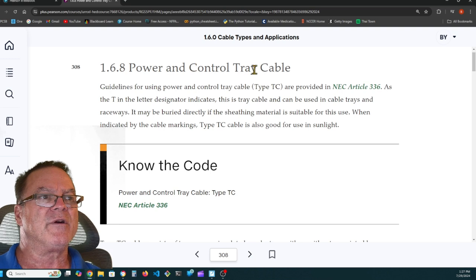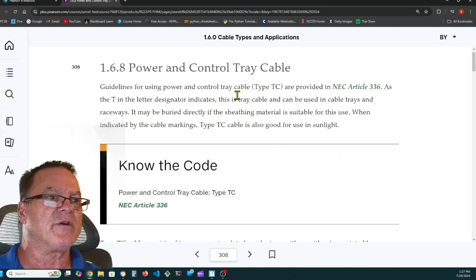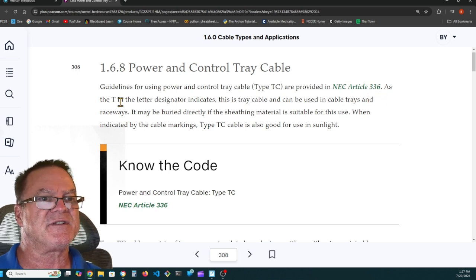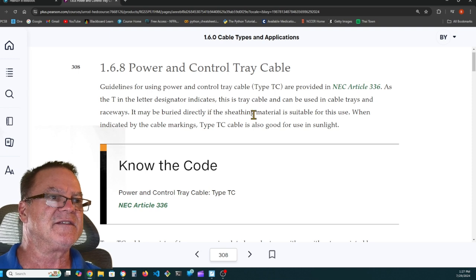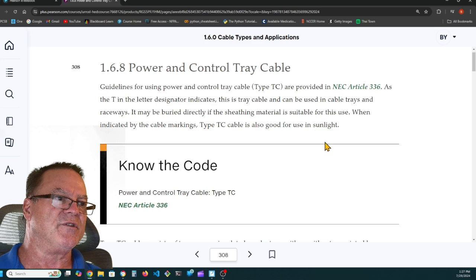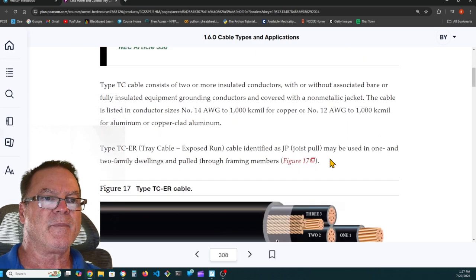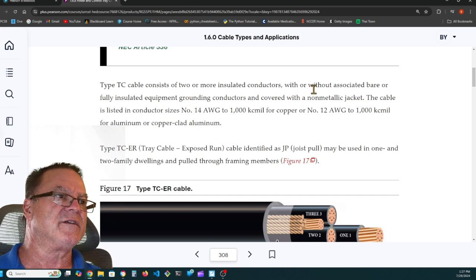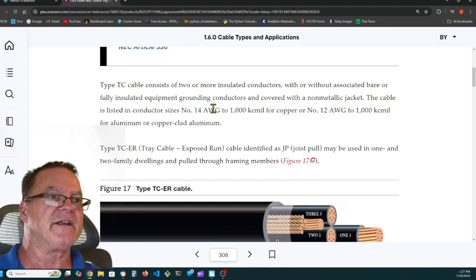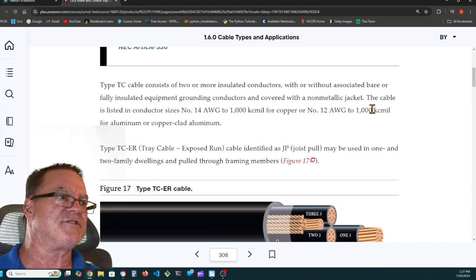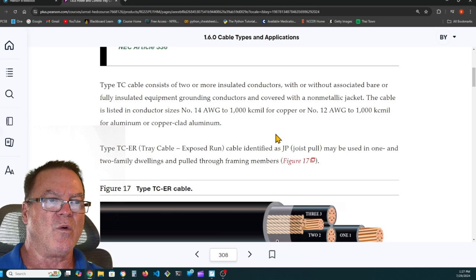1.6.8 Power and Control Tray Cables. Guidelines for using power and control tray cables are provided in NEC Article 336. As the T in the letter designator indicates, this is tray cable and can be used in cable trays and raceways. It may be buried directly if the sheathing material is suitable for the use when indicated by the cable marking. Type TC cable is also good for use in sunlight. Type TC cable consists of 2 or more insulated conductors with or without associated bare or fully insulated equipment grounding conductors and covered with a non-metallic jacket. The cable is listed in conductor sizes from number 14 gauge to 1000 kcmil for copper, or number 12 gauge to 1000 kcmil for aluminum or copper-clad aluminum.